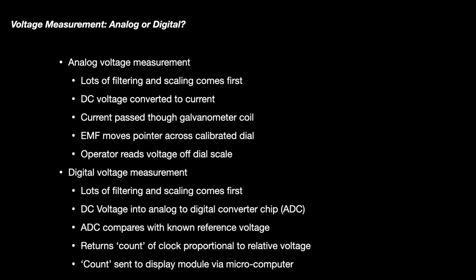So in a lot of these meters, the reference source is around 2.5 volts, 5 volts, or 7 volts, a Zener stabilized voltage source. And that becomes the basis for the comparison against the voltage that's being measured. So it's an indirect measurement, actually, when you're dealing with digital. And the more levels you have in the analog to digital converter, the more precision you have in the output of the device itself. Many of these instruments are around 16 bits, but some of them are up into the 24. About the best you can get off the shelf these days is around 32-bit.